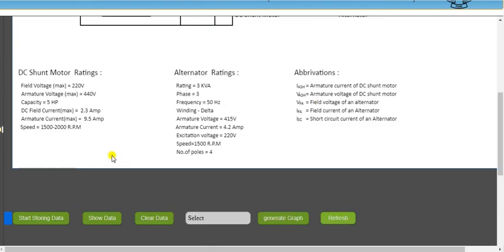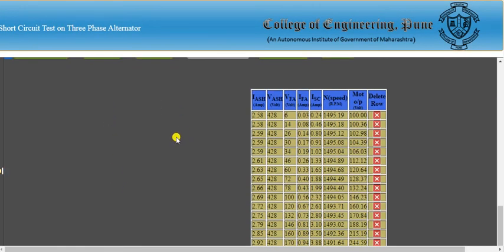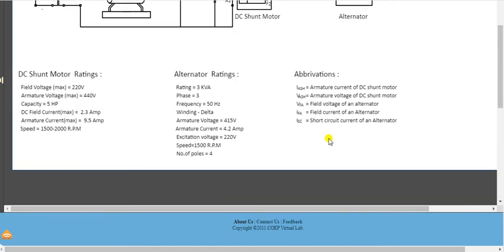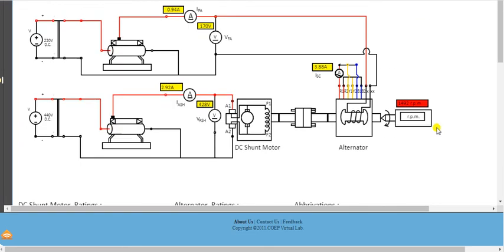The armature current reaches 3.88 A. You can also observe the motor output column and speed column — the speed is slightly decreasing. The first row showed 1495 rpm and the latest reading shows 1491.64 rpm, indicating a small drop in speed as field current increases.